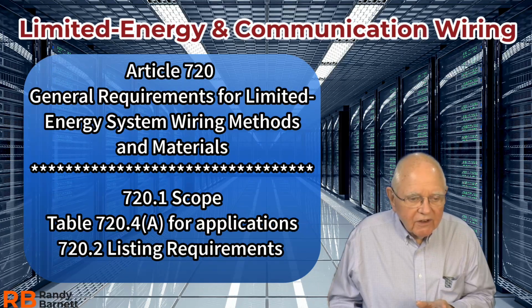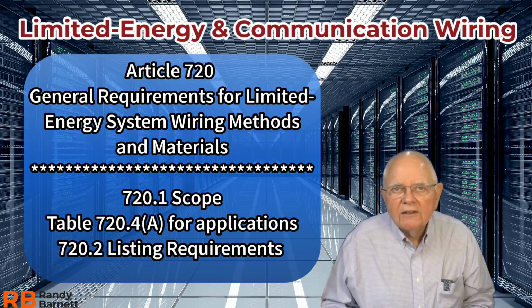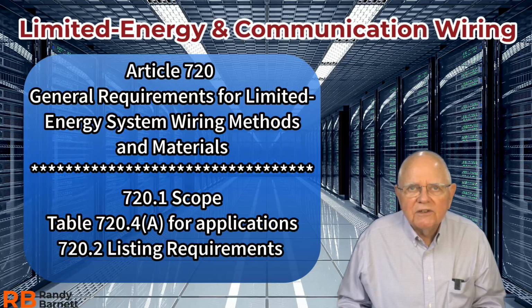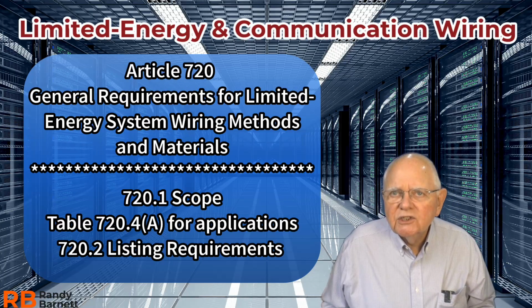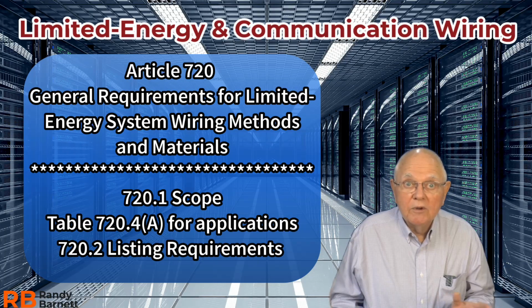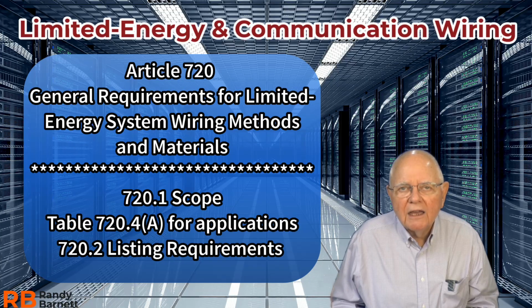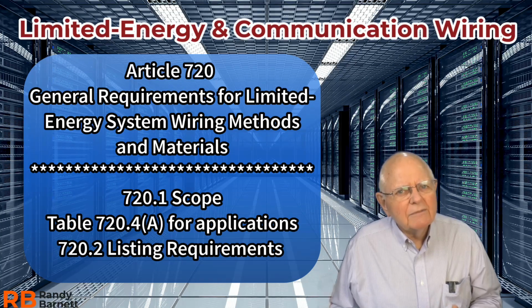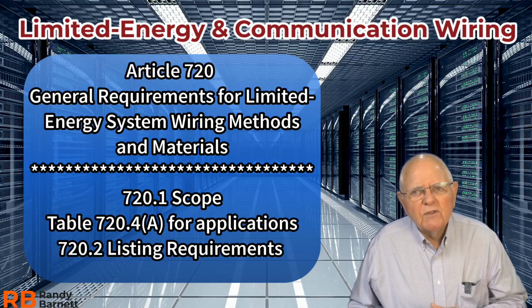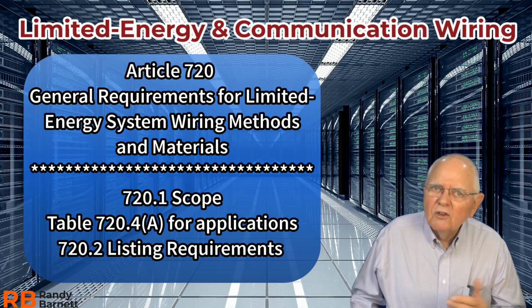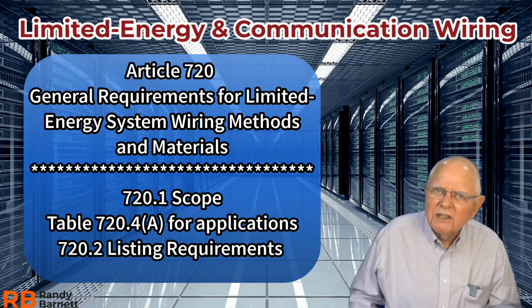Now, listing requirements, a global change throughout the NEC. .2 is now listing requirements. 720.2 says that communications equipment must be listed. Probably no surprise there. There is an exception, however, beware, an exception for temporary test equipment used by qualified persons. Doesn't have to be listed.